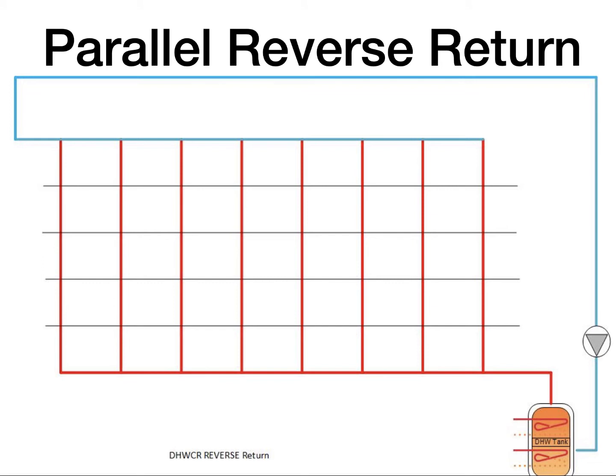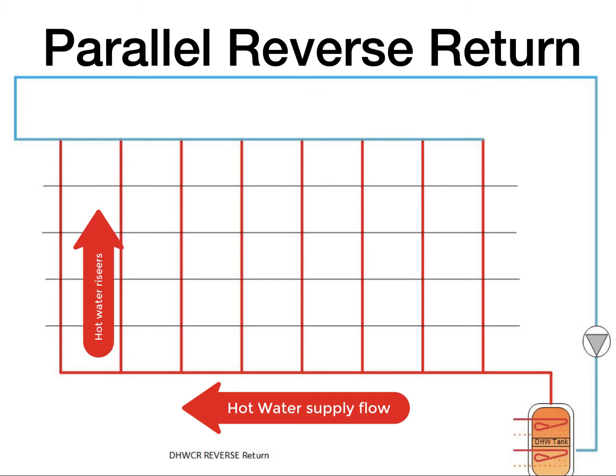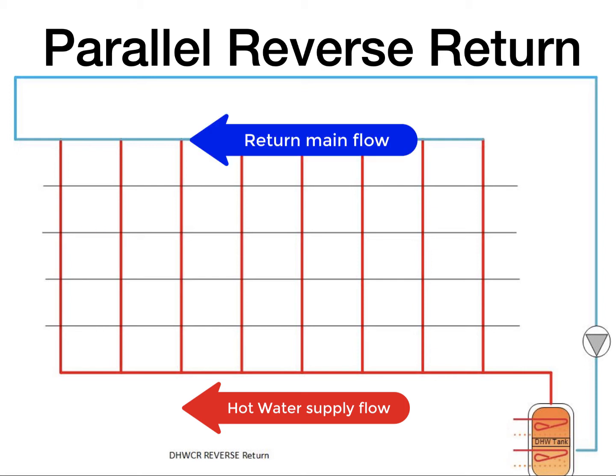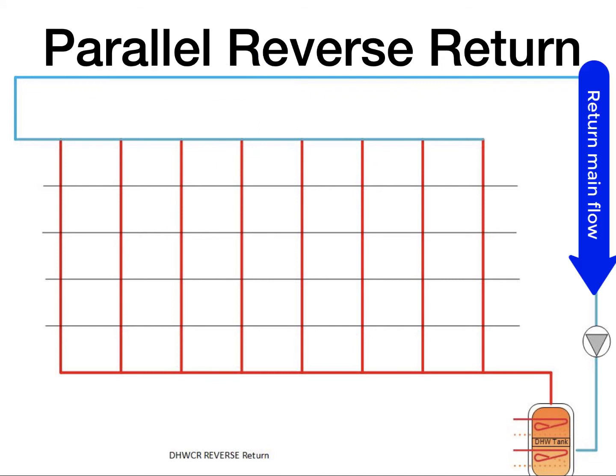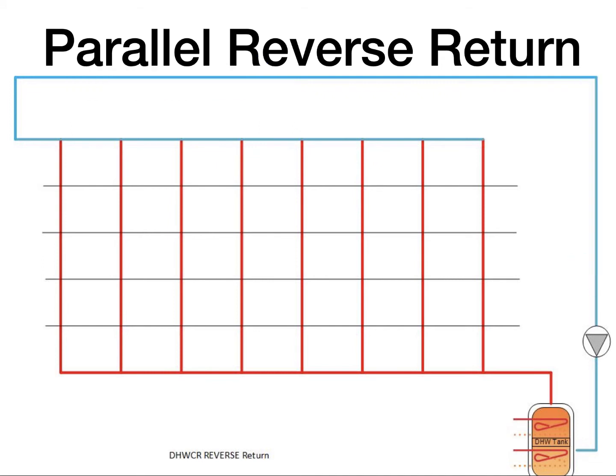This drawing depicts a parallel reverse return piping configuration with the same multiple floor multifamily dwelling application. The hot water supply main flows from right to left. The risers take the hot water up to the very top of the system where the beginning of the reverse return header begins. The return header also flows in the same direction as the hot water supplying into it, and then reverses and goes back down to the domestic hot water heating system source. This system is not as susceptible to problems associated with imbalances in flow.